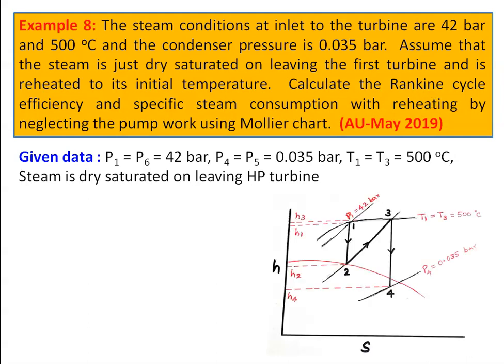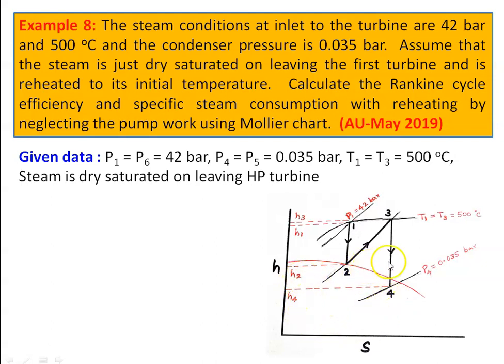This is the enthalpy-entropy diagram — the Mollier chart — a graphical representation. When you spread your Mollier chart, you may find a dark line — the red color line drawn here. That dark black line is called the saturation line. Below the saturation line we have wet steam, on the saturation line the properties of dry saturated steam, and above the saturation line superheated steam.